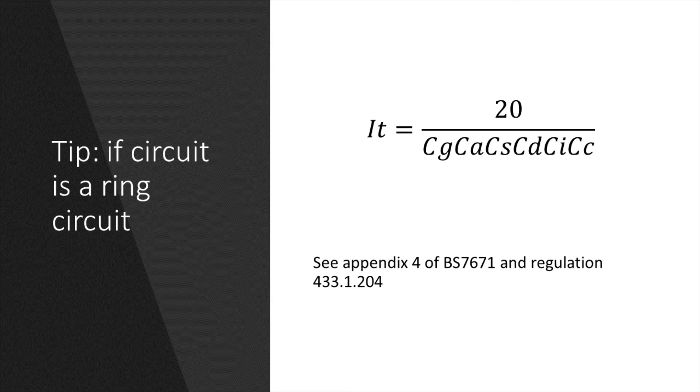So for this reason, when calculating the current carrying capacity for the cable, we can use 20 divided by the correction factors instead of the rating of the protective device. And you may find this useful when calculating the current carrying capacity IZ of the cable.